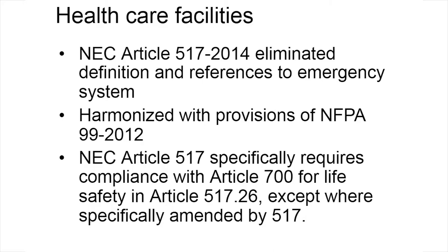517 specifically says that the life safety branch falls under the requirements of Article 700, except where 517 specifically amends them. So the wiring methods of Article 700 apply to the life safety branch, but the requirements for selective coordination, which are amended by 517, don't. It looks like the fire protection requirements of Article 700, which specifically apply to hospitals, will be enforceable on the life safety branch.